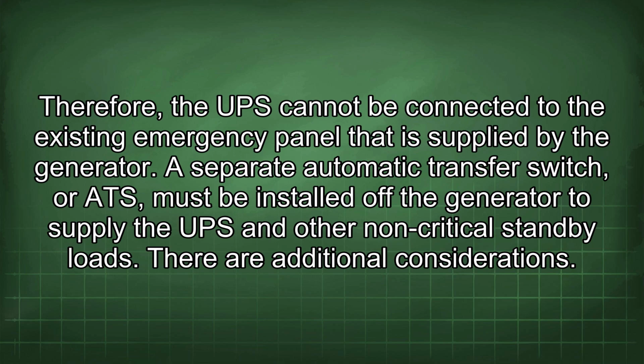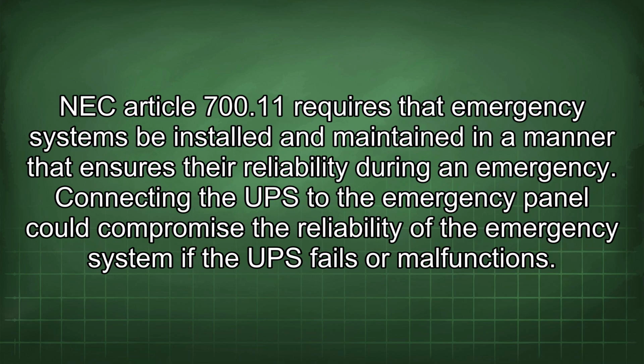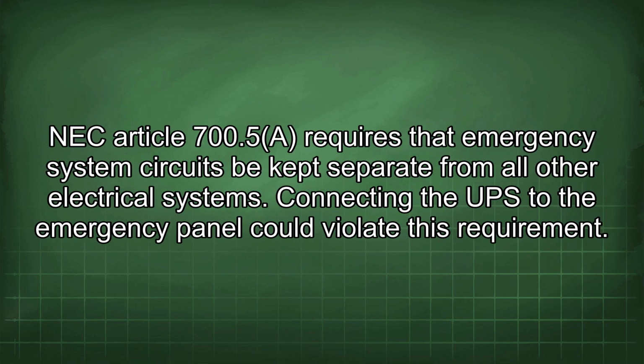A separate automatic transfer switch, or ATS, must be installed off the generator to supply the UPS and other non-critical standby loads. There are additional considerations. NEC Article 700.11 requires that emergency systems be installed and maintained in a manner that ensures their reliability during an emergency. Connecting the UPS to the emergency panel could compromise the reliability of the emergency system if the UPS fails or malfunctions. NEC Article 700.5 requires that emergency system circuits be kept separate from all other electrical systems. Connecting the UPS to the emergency panel could violate this requirement.